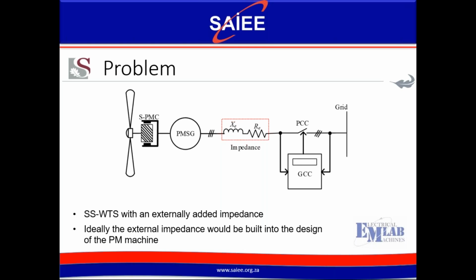Yeah, thanks, Dillan. The next question, from Peter Fick: what will be the losses of the additional reactance between the generator and the grid in reference to the power generated by the generator? If I understand that question, is it what would be the added losses caused by the externally added impedance? Yes, that's it. That would vary, as the losses are a function of the wind speed, which varies considerably. But obviously we'd want to minimize those losses, and those losses are purely a function of that external impedance.